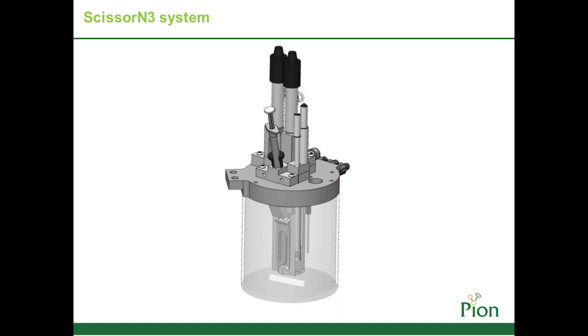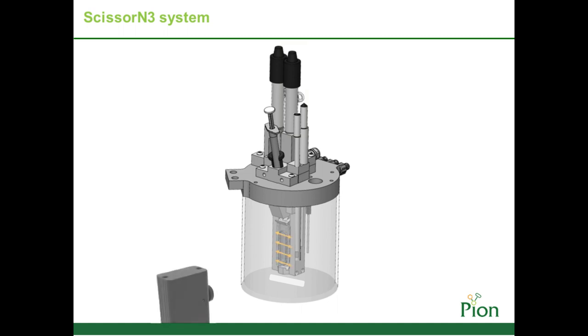The system also monitors pH at the injection site to observe any pH stresses on the formulation, and we have turbidity sensors and cameras for each chamber to observe any physical instability upon injection and over time. The release data coupled with turbidity, pH, and imaging data helps gain a fuller picture of what's happening to the drug upon injection and how these events will affect uptake in vivo.